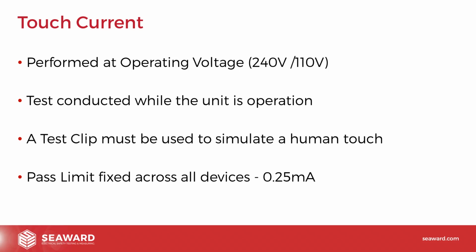The clip, and is that current high enough to cause us an issue? In the case of a touch current test, it's pretty much performed only on double insulated or class 2 products where there isn't an earth. So therefore the clip is also acting as the return back to the device.